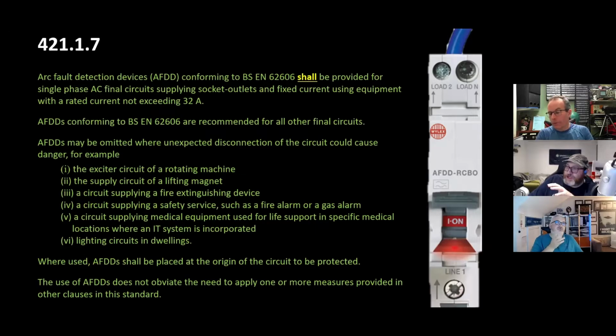So if you had this situation, also they're huge, you double the size of the internal gubbins for type B. If you had equipment that required a type B, you'd have to have a separate module AFDD from your RCBO, wouldn't you, for charging points? Yeah, but you wouldn't use an AFDD, the technology's not mature enough for that yet.